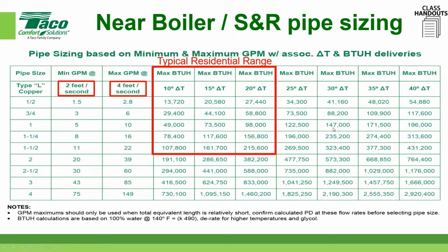What that might mean is the boiler primary piping might be 1 inch because it's relatively short, but my secondary header might be 1.25 inches. Okay, so just keep that in mind. Where can I save money? Well, by being smart, by sharpening my pencil, by dotting the I's and crossing the T's, and that's where these little quick lookup columns will help you out.